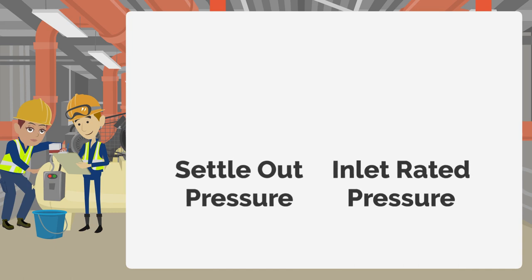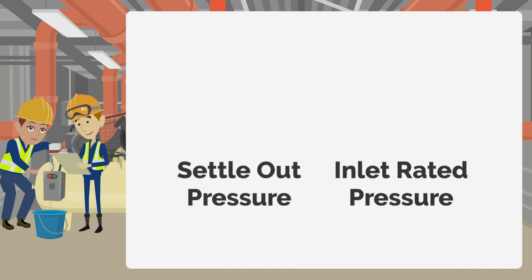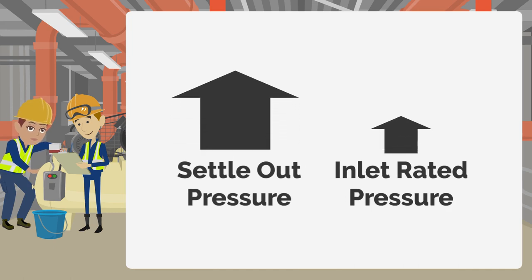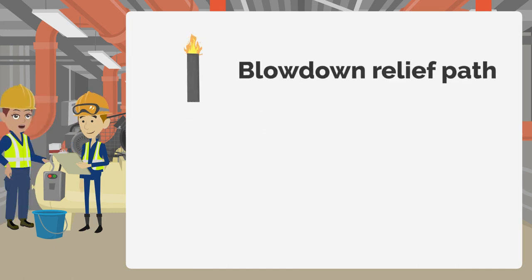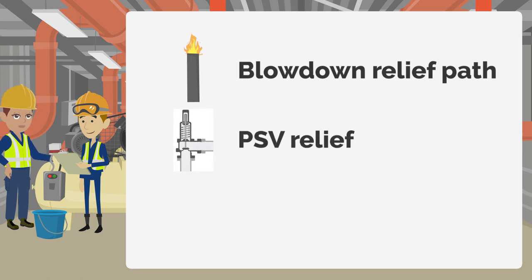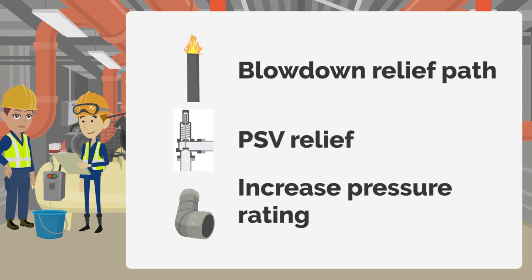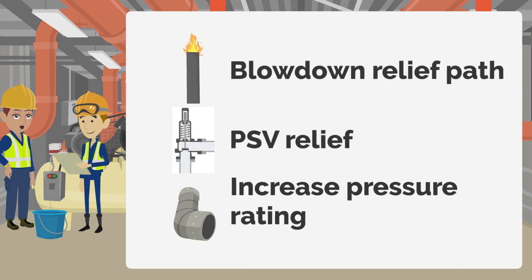Second, if the settle-out pressure is above the rating of the compressor inlet, having a blowdown relief path, a pressure safety valve set for settle-out pressure, or increasing the pressure ratings at the compressor or pump inlet are options to prevent settle-out overpressure.